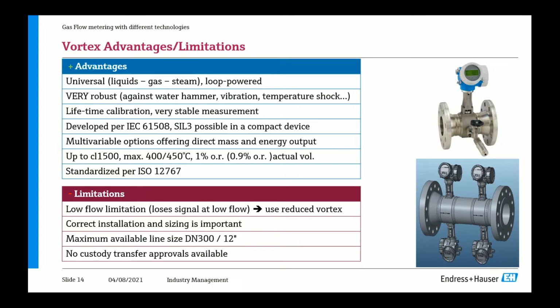It's the first vortex meter developed per IEC 61508, so really not only proven in use. And we can offer you SIL 3 devices in a single device, like the dual sense, that's 1 out of 2, or we can also offer you 2 out of 3 architectures. We have multivariable options offering direct mass and energy output, so you get the MMBTUs directly out of the meter. It's available up to class 1500, max 450 degrees C, and the best accuracy you can get is 0.9%. And they're standardized per ISO 12767.